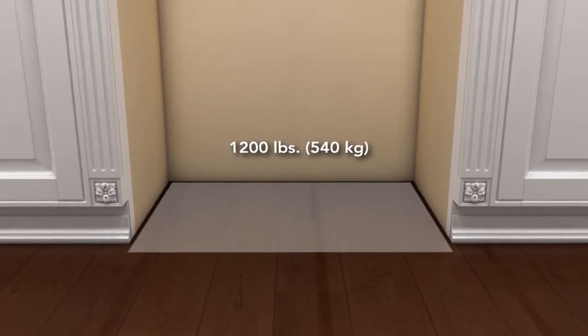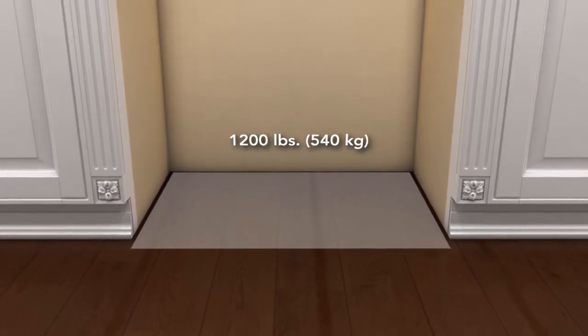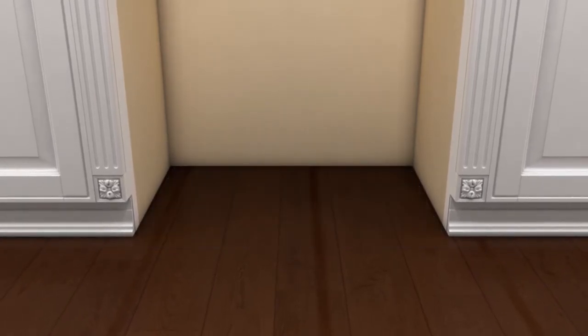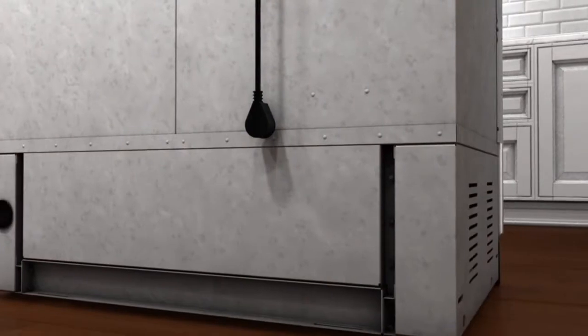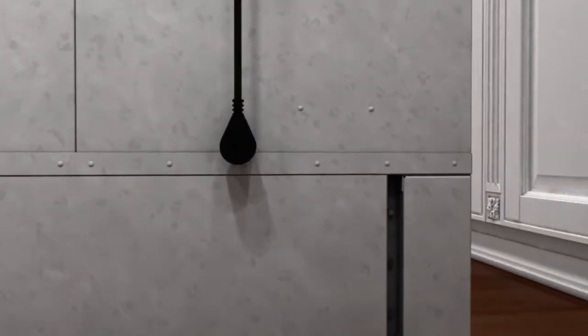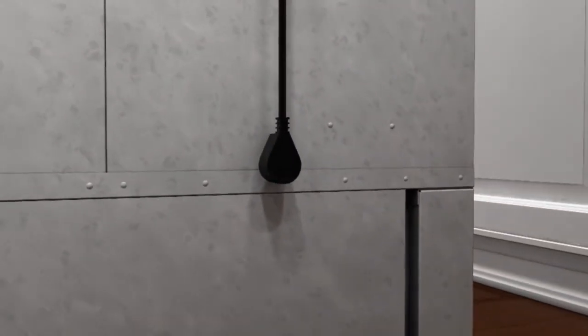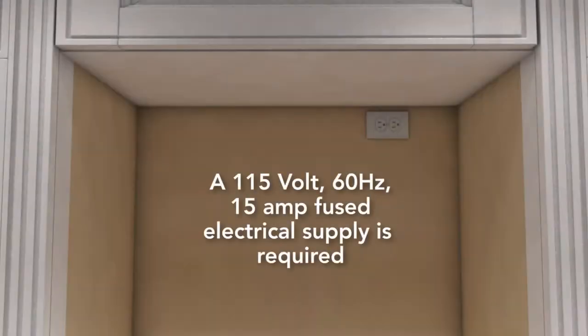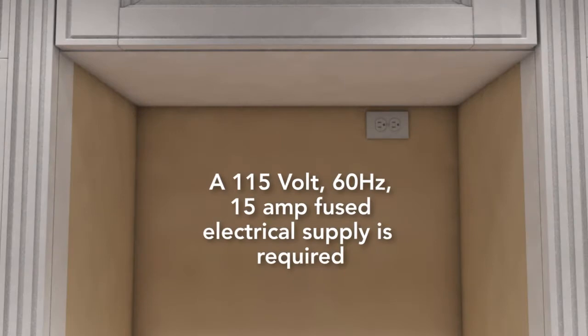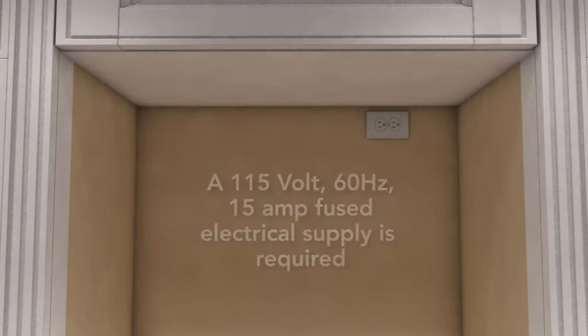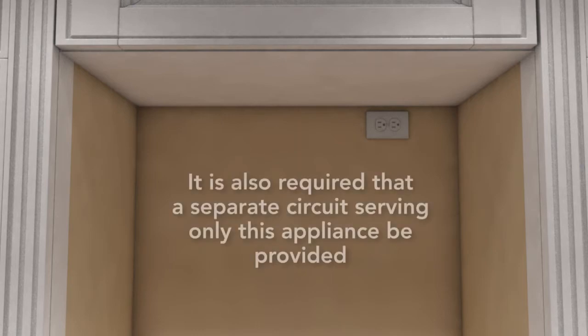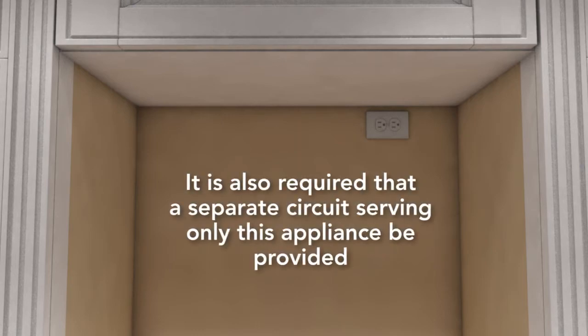Ensure the floor substructure will support the weight of the unit, which is approximately 1200 pounds. The appliance is equipped with a three-prong grounding plug. A 115-volt, 60-hertz, 15-amp fused electrical supply is required. It is also required that a separate circuit serving only this appliance be provided.